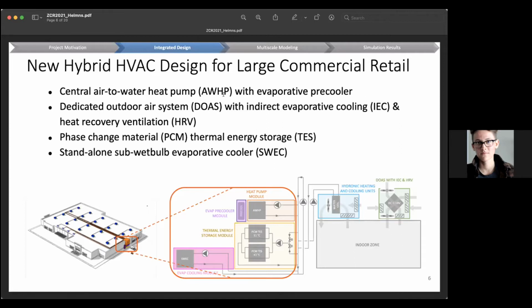All of the systems we've designed have an air-to-water heat pump, which is what you're seeing here. An air-to-water heat pump basically uses air as a thermal reservoir and pulls or rejects heat to that air to condition water. This water then flows through the rest of the system, and it will be hot or cold.